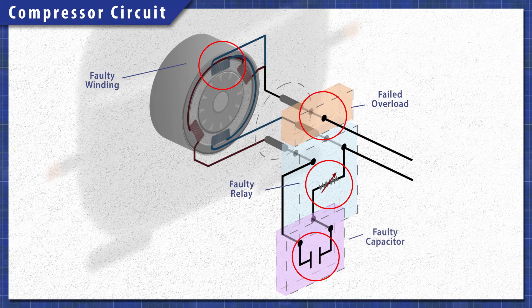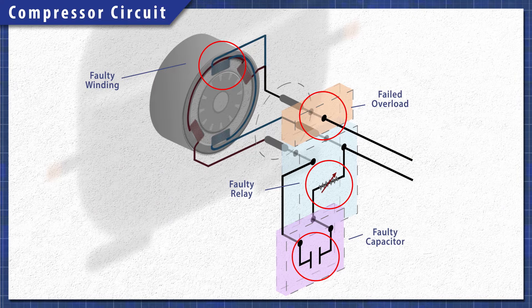Regardless of the model, a faulty motor winding, a bad overload, relay or capacitor can all prevent the compressor from starting.